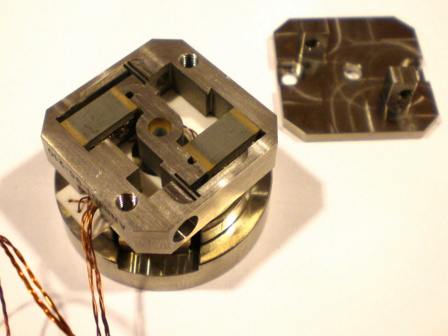The non-powered behavior of the first type of piezoelectric motor is one of two options, normally locked or normally free. When no power is applied to a normally locked motor, the spindle or carriage for rotary or linear types, respectively, does not move under external force. A normally free motor's spindle or carriage does move freely under external force.